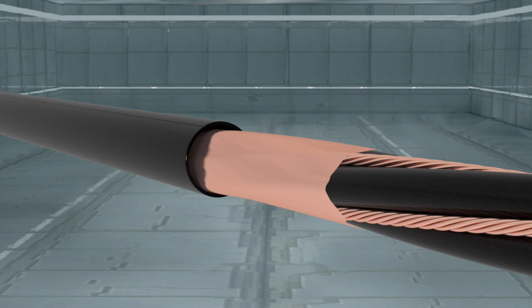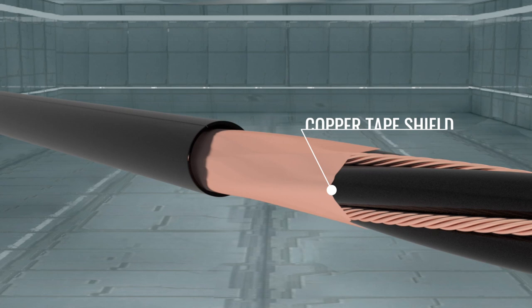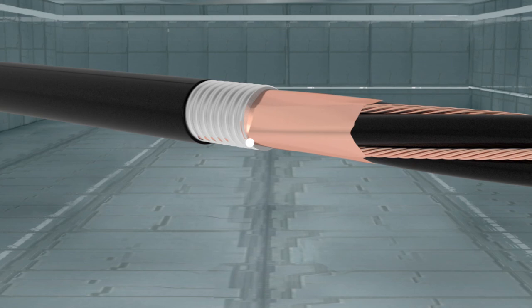Three thermoset insulated conductors are cabled together with three balanced grounds. Then, a flat copper tape shield is helically applied with 50% overlap to provide a low impedance return path for the high-frequency current, available in UL-type TC-ER tray design or jacketed type MC, which can eliminate the need for conduit.